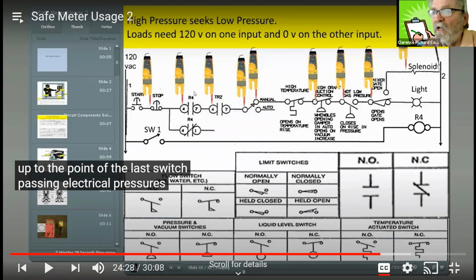If R4 is going to close, something's got to close switch 1. So if something closes switch 1, R4 is going to close. Then we're going to have 110 volts going through here. TR2 is someplace, and wherever that is, we've got to energize that coil and wait for that time to time out. And then we get to have 110 volts here.